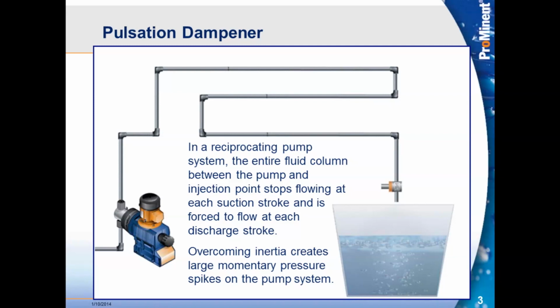That cavitation, where we have the flow going in one direction and we're trying to pull back on it in the opposite direction, that is a cavitation for us, and that is a very critical thing. Again, the larger the volume per stroke, the more important it is for us. So now the longer the discharge run, we have a larger volume that we're dealing with, even if it's a smaller pump. So we have to be very aware. We don't want that long of a run on the discharge, and especially when we get into pumps that are rated with a higher volume per stroke, we want to start very much insisting that a pulsation dampener is one of the critical items that we include with it.